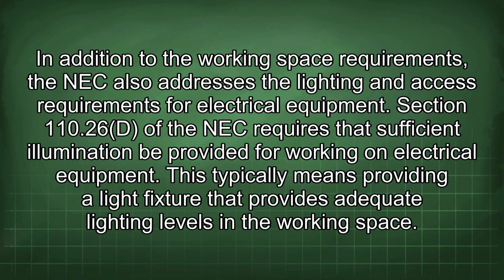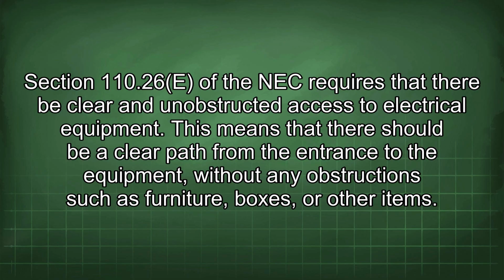Section 110.26(D) of the NEC requires that sufficient illumination be provided for working on electrical equipment. This typically means providing a light fixture that provides adequate lighting levels in the working space. Section 110.26(E) of the NEC requires that there be clear and unobstructed access to electrical equipment. This means that there should be a clear path from the entrance to the equipment, without any obstructions such as furniture, boxes, or other items.